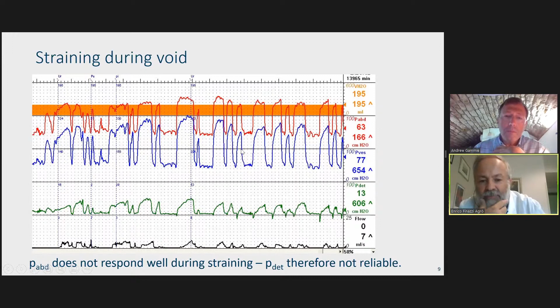Yes, absolutely, Andrew. And sometimes, again, if you are not an experienced urodynamicist, you may just take the results from your machine, and your machine can tell you that the maximum detrusor pressure was, I don't know, 50 centimeters of water, but this was not true. This was just because there was this difference in recording between the P-ves and the P-abd. So again, it's an artifact. It's not a real pressure.